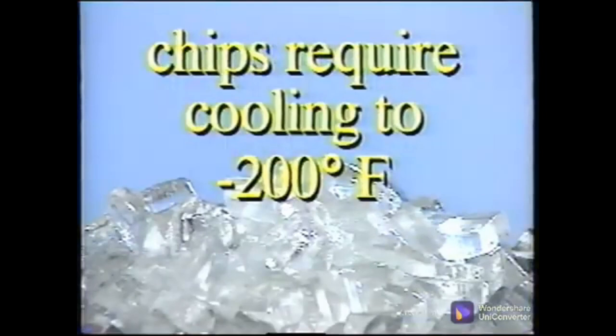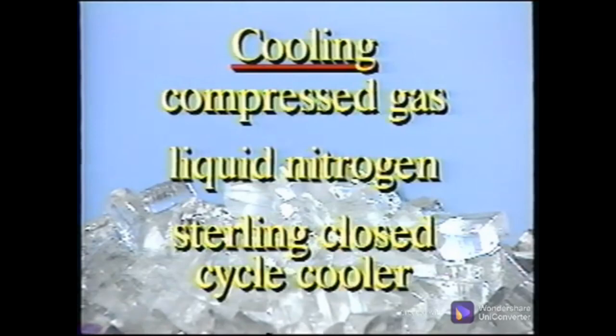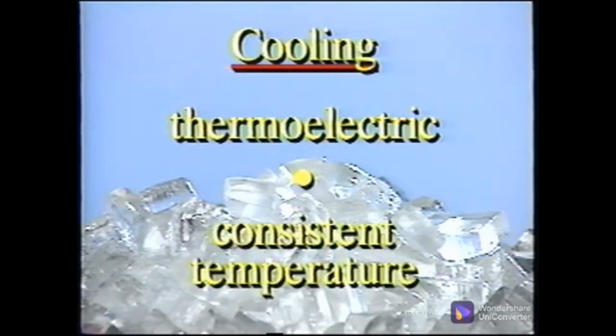Many of the detectors used in a single element or focal plane array must be cooled to obtain the response needed to provide a high resolution image and accurate temperature measurements. The cooling can be through a compressed gas, liquid nitrogen, a Stirling closed cycle cooler, or thermoelectric cooling. Whatever the cooling method, a consistent temperature in the camera must be maintained for the best accuracy.